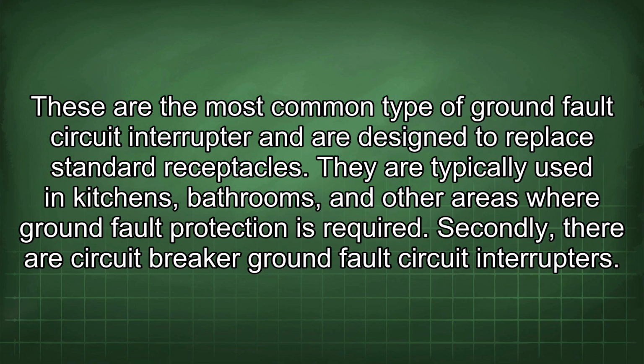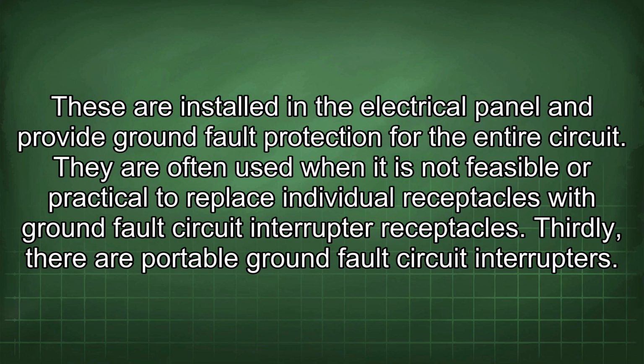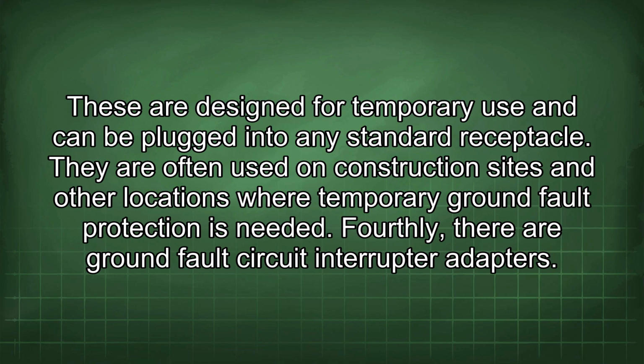Secondly, there are circuit breaker ground fault circuit interrupters. These are installed in the electrical panel and provide ground fault protection for the entire circuit. They are often used when it is not feasible or practical to replace individual receptacles with ground fault circuit interrupter receptacles. Thirdly, there are portable ground fault circuit interrupters. These are designed for temporary use and can be plugged into any standard receptacle. They are often used on construction sites and other locations where temporary ground fault protection is needed.